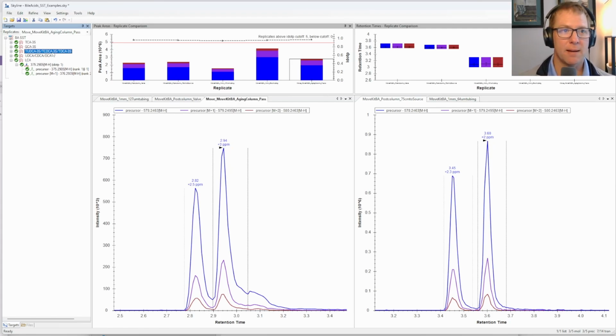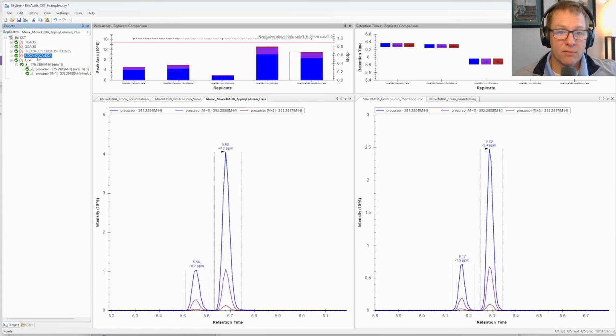These are sulfated metabolites. When you see something like this on the left, you may be tempted to say, oh, I've got post-column broadening somewhere. The way that you know it's not post-column broadening and it's something else going on is the fact that the fidelity of later metabolites, or other molecules in the separation, is good. That's the telltale sign.